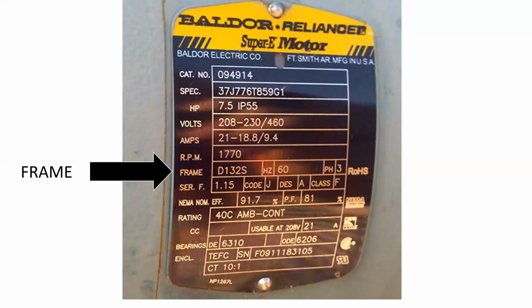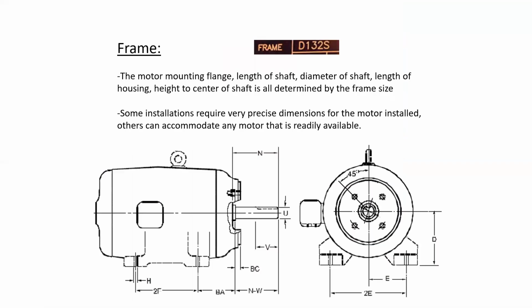The frame of the motor. The frame on this motor is D132S. The frame of the motor is really in relation to the motor mounting flange. The length of the shaft, the diameter of the shaft, length of housing, and height to center of shaft are all determined by this number. Some installations really do require a very precise dimension for the motor installed. Others can accommodate any motor that is readily available. So of course, this is going to be something that is looked up through the manufacturer to ensure that you have the right motor for the application.